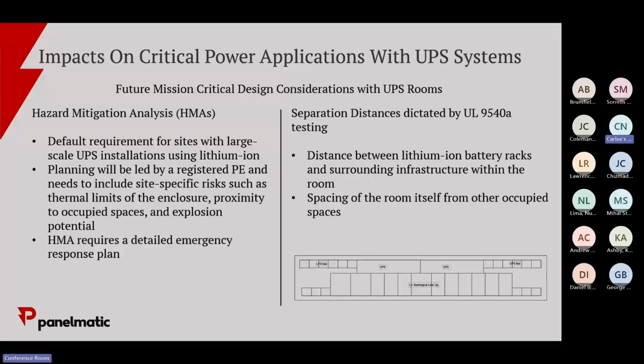If this was sitting outside, beside some generators for instance, these boxes, because of the batteries, would have to be 10 feet away. That's what I'm saying, but you're showing your battery here, and this is an old design. So in a new design, this would be 3 feet off the wall, and you could take this row of batteries and that row of batteries, put them in front of each other, 3 feet off the back wall, and now you have enough clearance to put 2 rows.